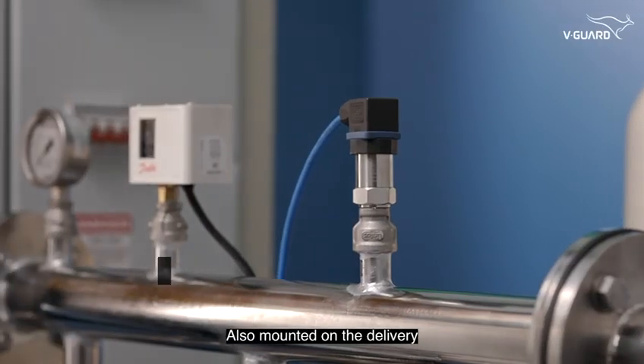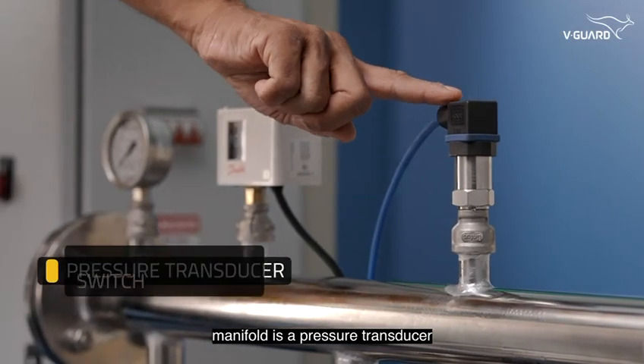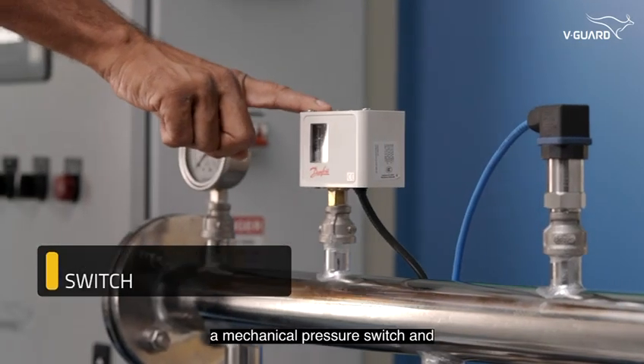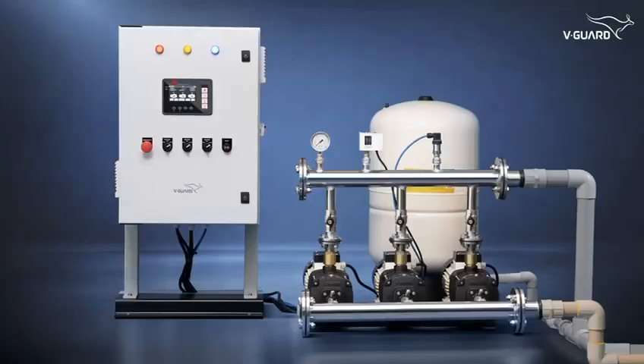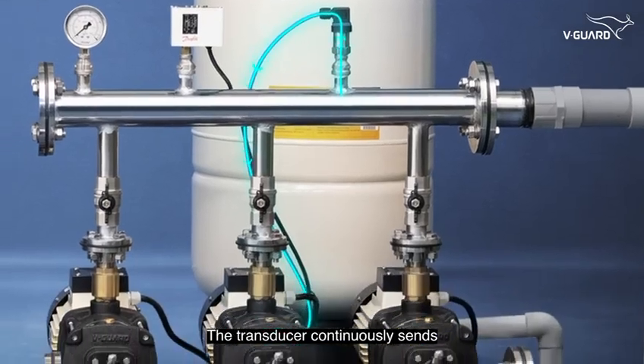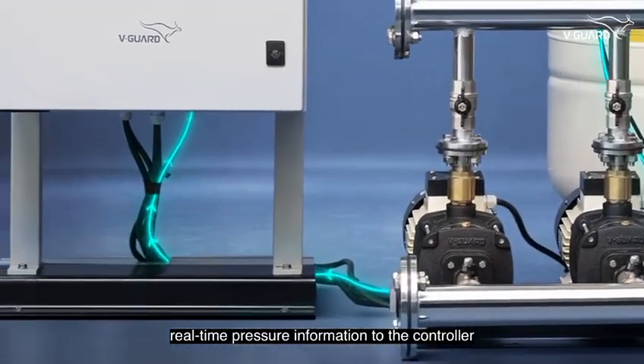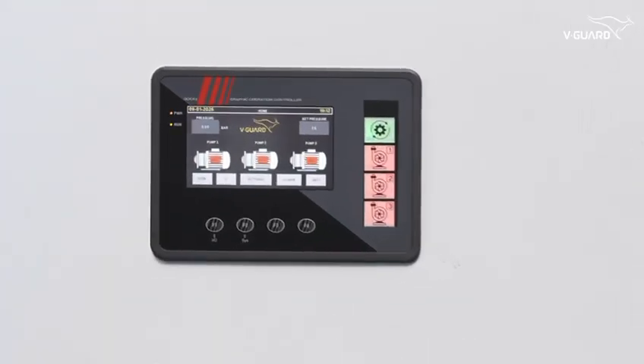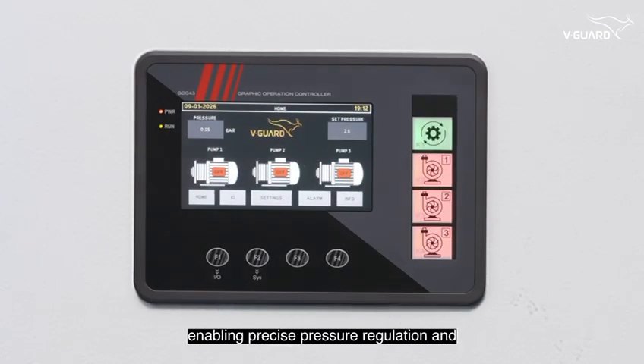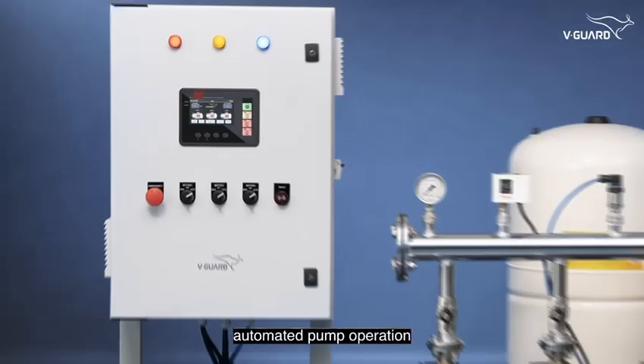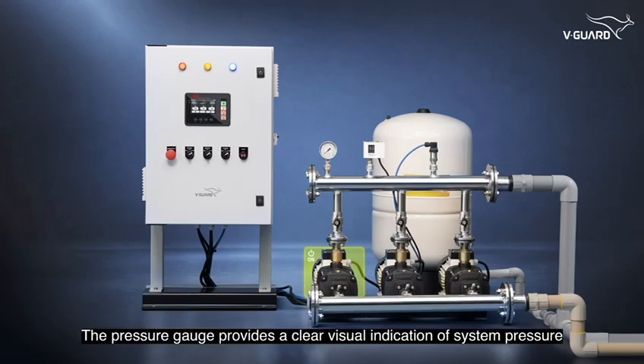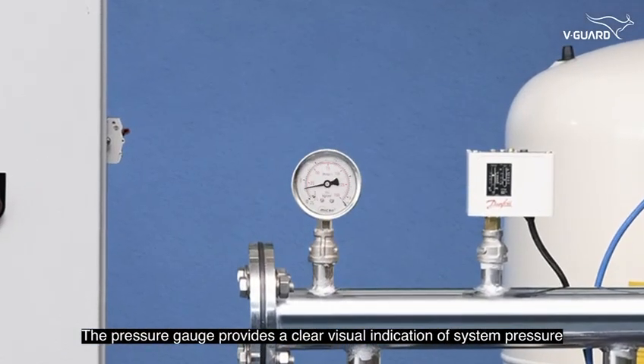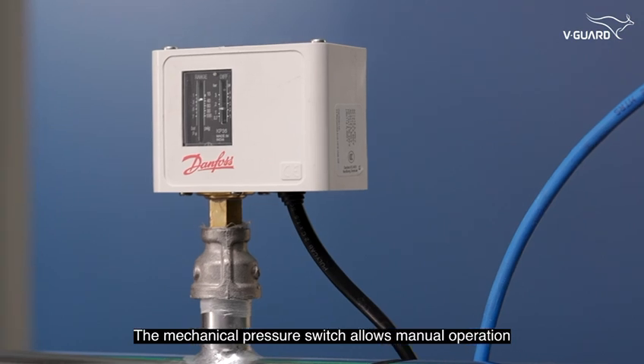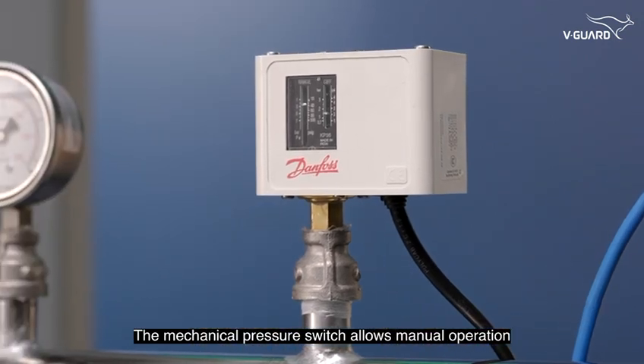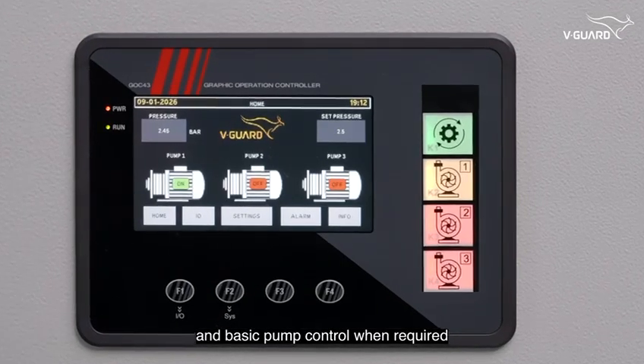Also mounted on the delivery manifold is a pressure transducer, a mechanical pressure switch and a pressure gauge. The transducer continuously sends real-time pressure information to the controller, enabling precise pressure regulation and automated pump operation. The pressure gauge provides a clear visual indication of system pressure. The mechanical pressure switch allows manual operation and basic pump control when required.